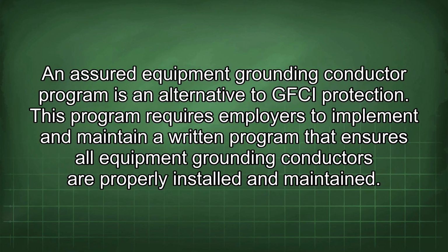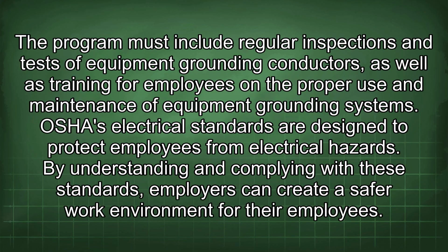An assured equipment grounding conductor program is an alternative to GFCI protection. This program requires employers to implement and maintain a written program that ensures all equipment grounding conductors are properly installed and maintained. The program must include regular inspections and tests of equipment grounding conductors, as well as training for employees on the proper use and maintenance of equipment grounding systems.